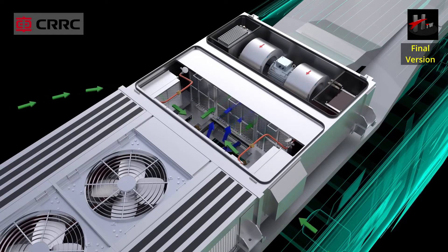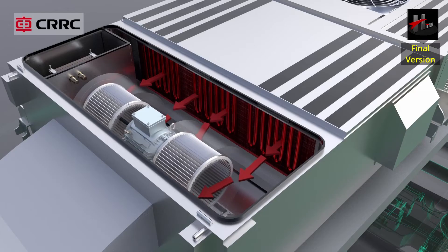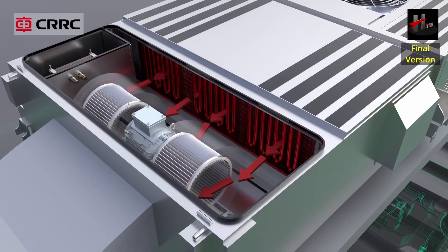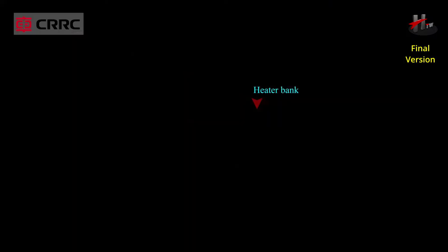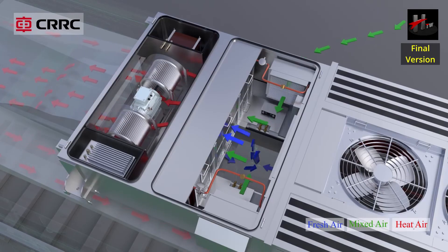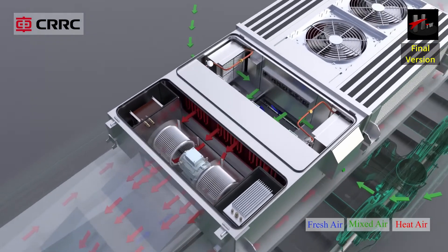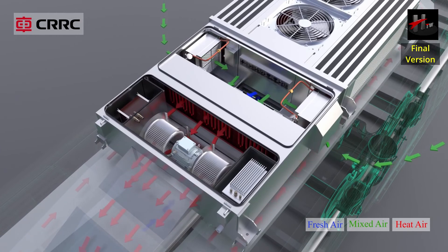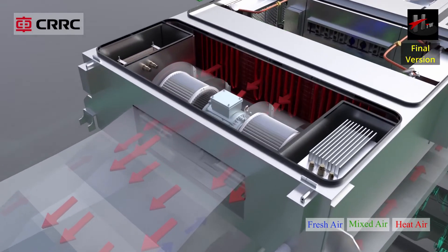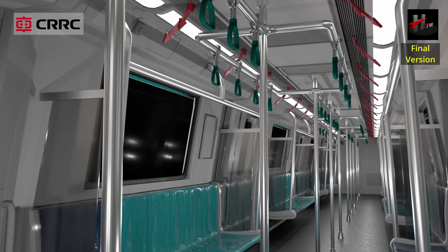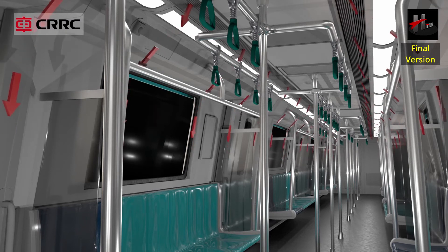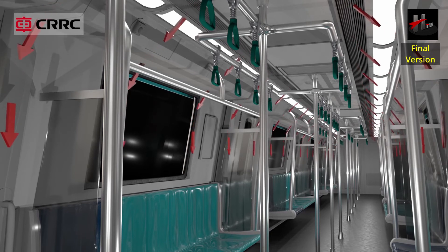From the mixed air chamber, the mixed air of ambient and return air passes through the mixed air filters and the heater bank. The heater bank heats the mixed air before it is supplied into the supply air duct through the supply air opening, and warm air is discharged into the saloon through the air diffusers located in the ceiling of the saloon car.